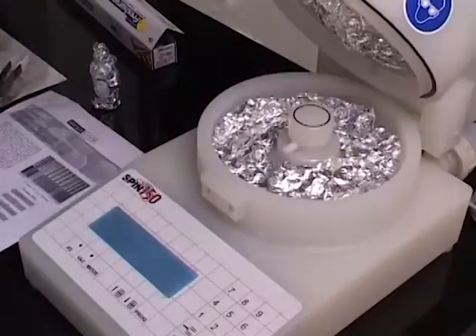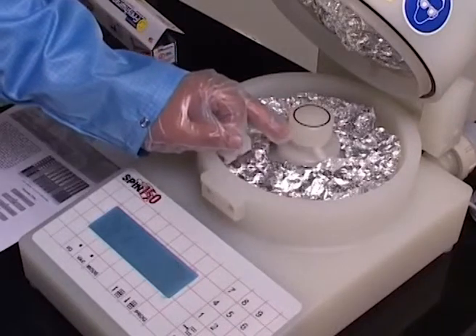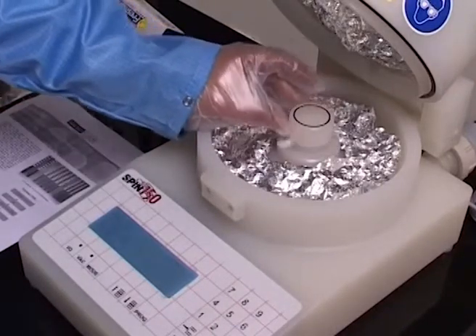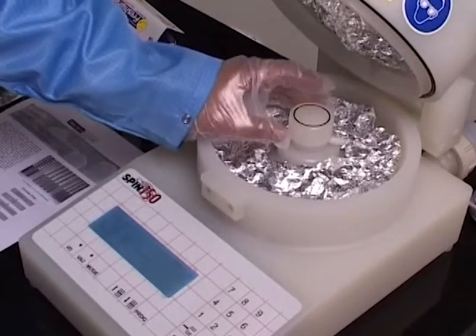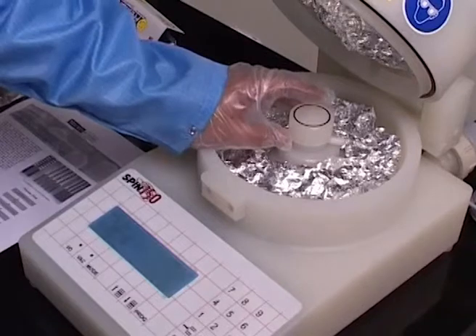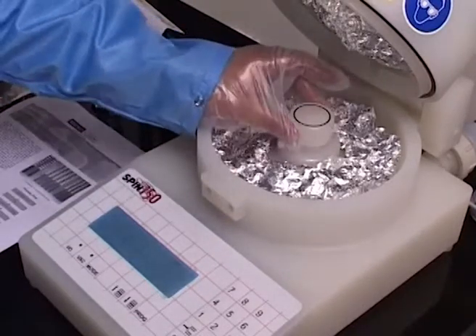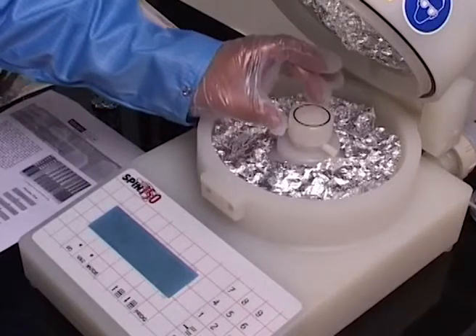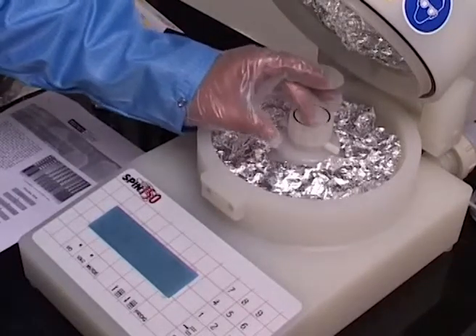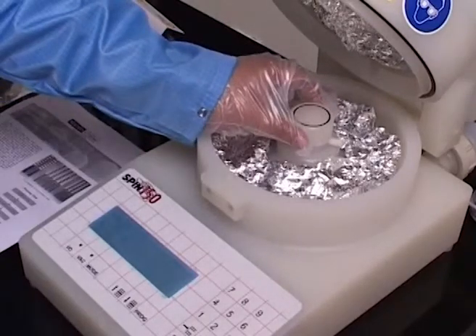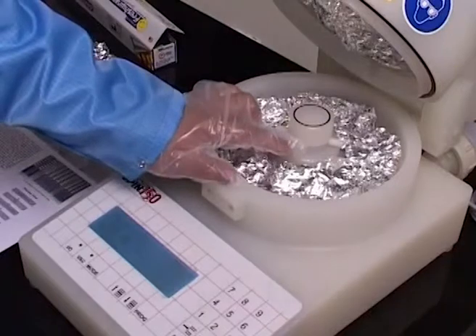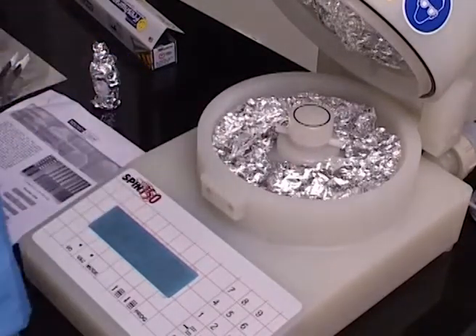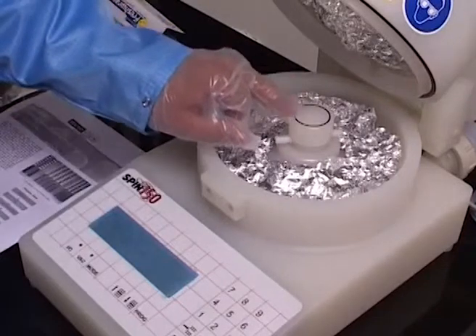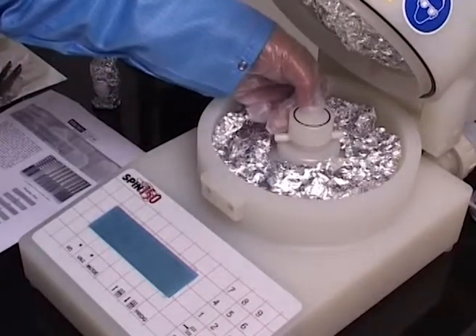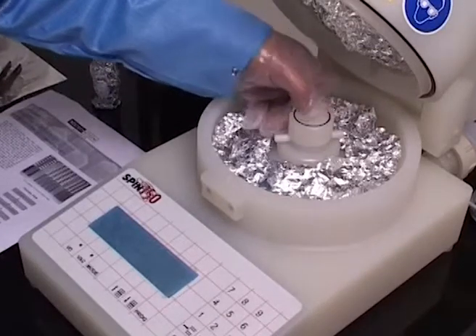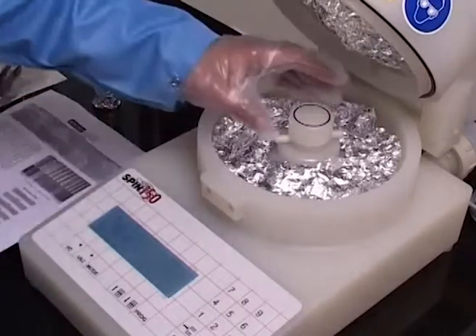If you look into this machine closely, you have a spin stage, which is here in this area. The principle is that you use vacuum for holding the wafer onto the spin table. If you look closely, you have these crisscross grooves placed over the whole periphery of the spin stage. There is a vacuum track immediately below this, connected to a vacuum pump underneath the whole system. The vacuum propagates all the way up through this small center hole and also along these grooves, and holds the wafer on the top of the surface.